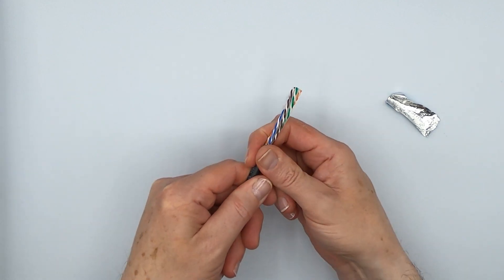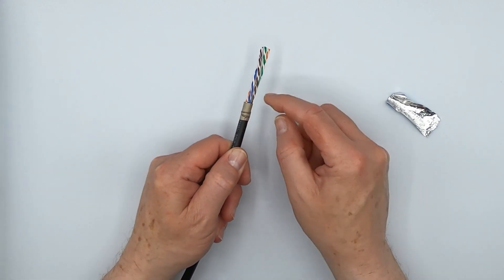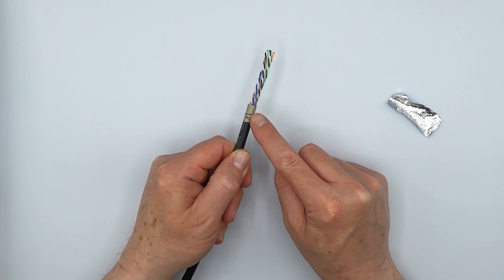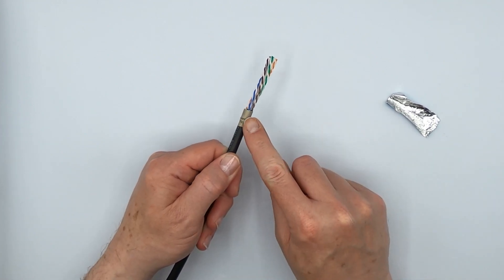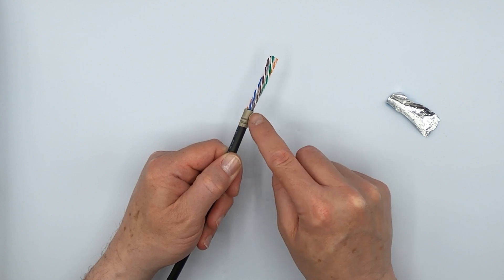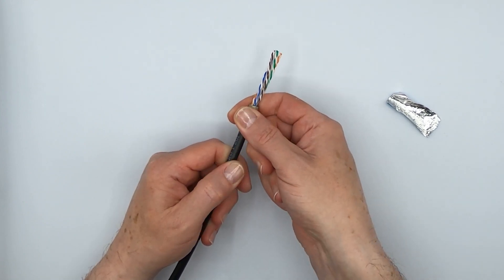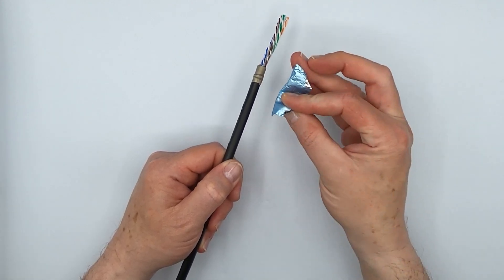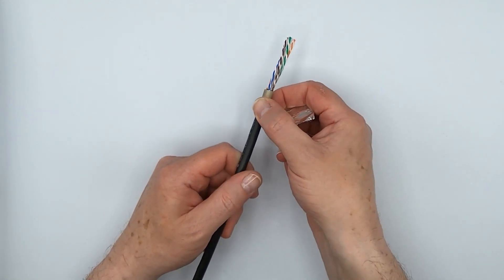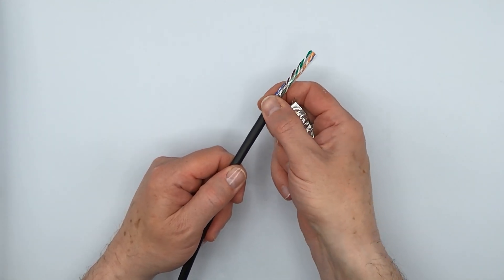The drain wire has now been tacked down. The conductive adhesive is making contact with the drain wire. And that's going to transfer electromagnetic energy through this copper fabric and into your termination hardware. And you don't have to deal with this annoying cable shield getting in your way. You don't have to worry about trimming it off. It's ready to go.